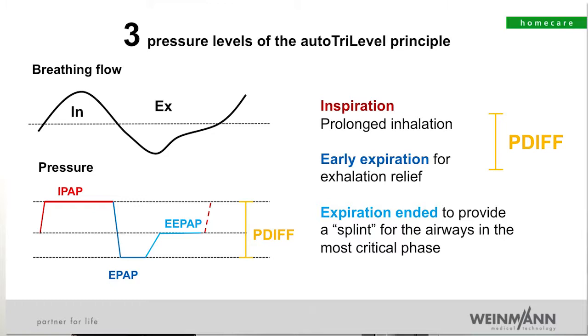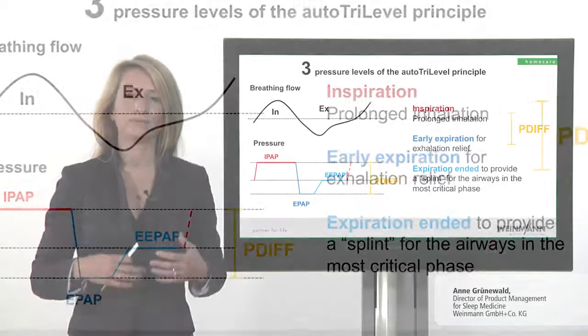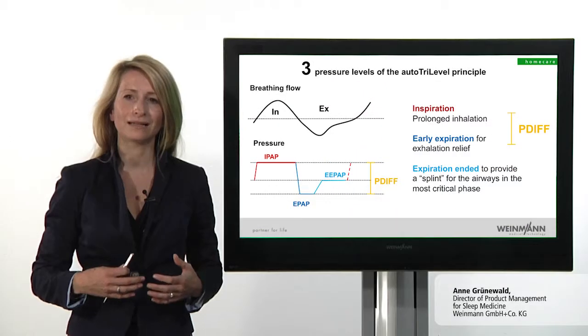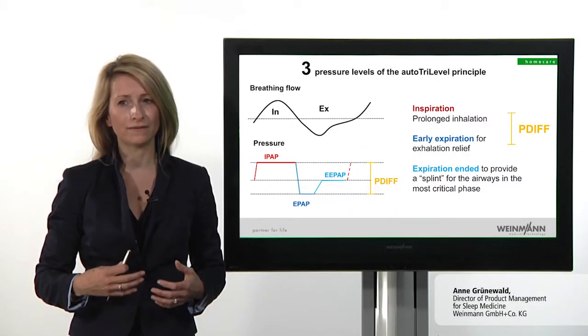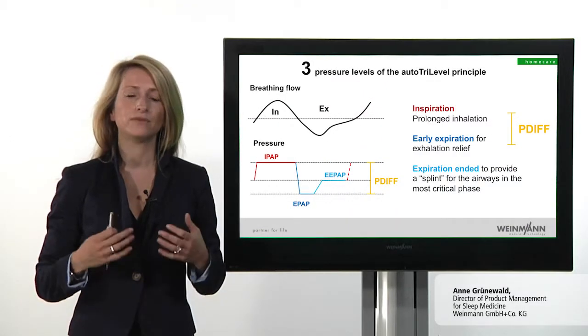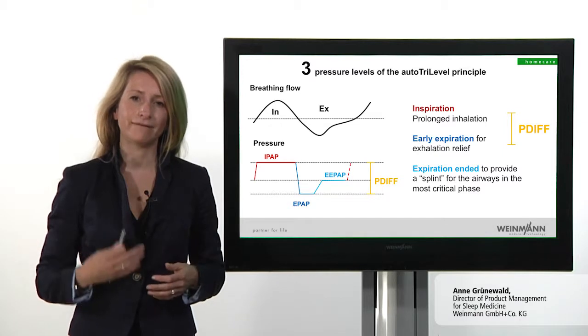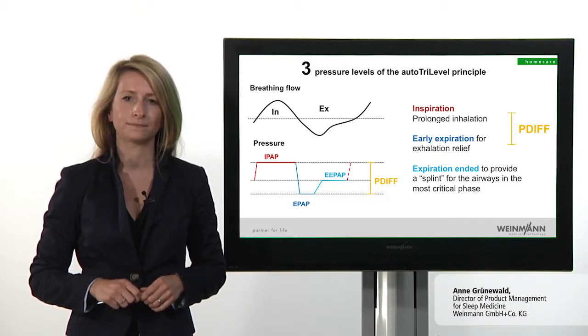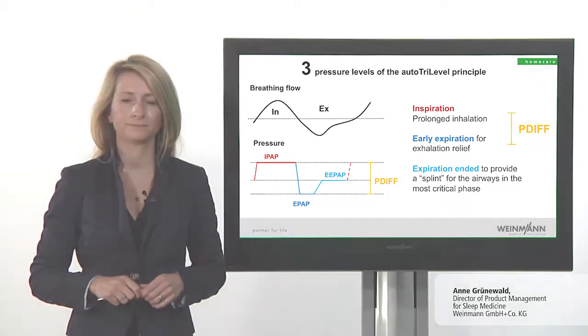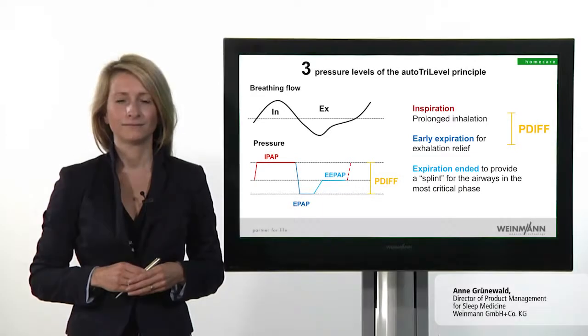Automatic regulation of the PDIFF ensures first and foremost controlled ventilation according to need when the patient requires more ventilation, and it effectively prevents central apneas when the backup frequency is operating.